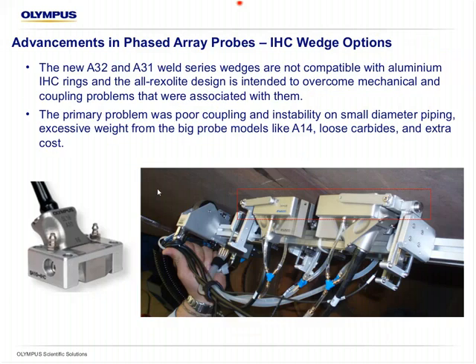The new A32 and A31 Weld series wedges are not compatible with the aluminum IHC rings, and the all-Rexolite design is intended to overcome some mechanical and coupling problems that were associated with the large versions of them. The primary problems on large versions of these that were not reported on the smaller versions were the coupling and instability on smaller diameter piping with large probes, and excessive weight from the big probe models like the A14, which had some repeatability issues at 9 and 3 o'clock if not controlled very well by the operator and using the appropriate springs and number of springs.